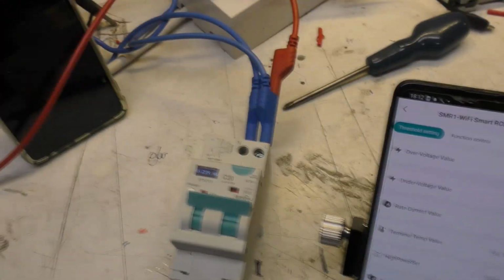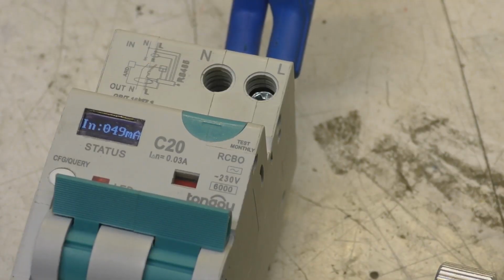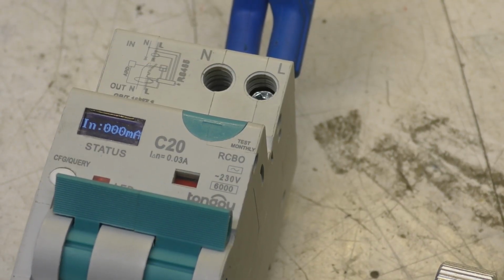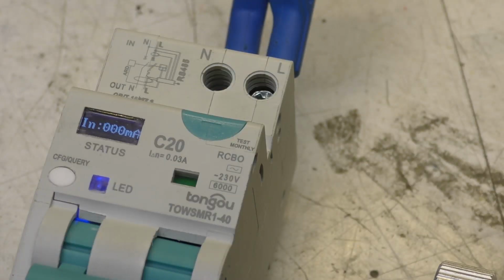If we look at the display, you see that's about 49 milliamps, and it's not tripping. Yeah, that leakage current display is potentially very useful in certain scenarios. The test button still works, and although we can set this current to whatever we want, we probably wouldn't want to set it below 30 because of capacitance and just normal leakage that you get from things like EMI filters. But of course, you can just turn it off.